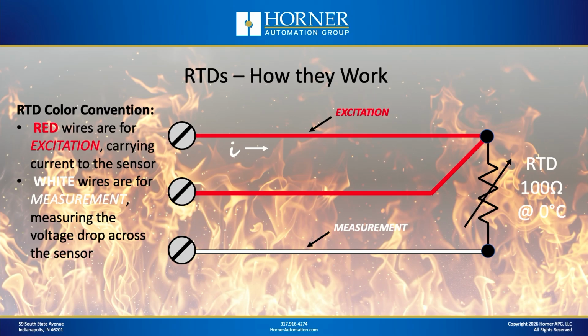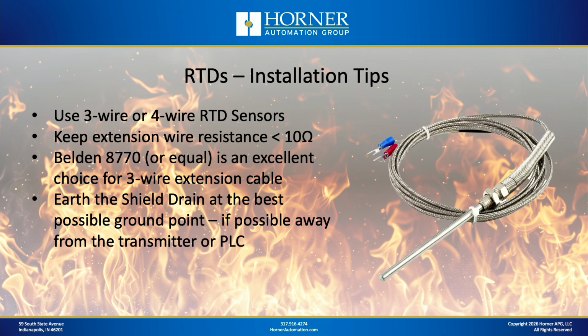All right, in terms of the color conventions with RTDs, this isn't quite as universal as with thermocouples, but almost all reputable RTD manufacturers are going to have red leads for the excitation leads that are on one side of the sensor and white leads for the measurement lead. So that's what you're typically going to find: 2 red leads and 1 white lead for a 3-wire RTD. When we talk installation tips, you're never going to want to use a 2-wire RTD. So it's going to be a 3-wire or a 4-wire. And if you're talking an industrial application, almost always it's going to be a 3-wire lead.